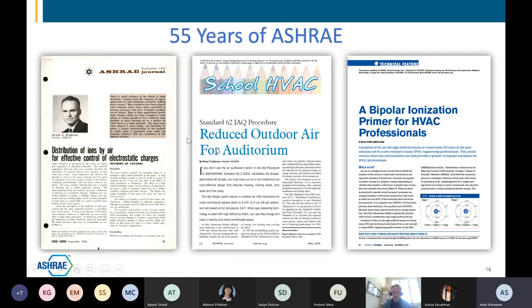In the center is an article that appeared in May 2006, again, another peer-reviewed ASHRAE journal article that talked about using bipolar ionization through the ASHRAE standard 62.1 IAQ procedure to reduce outdoor air and to save energy. It showed a profound impact on energy savings as well as its impact on making the air cleaner. And it also won ASHRAE's 2006 Technology Award for advanced, I don't remember exactly what they called it, but I think it was Advanced Application HVAC Systems.